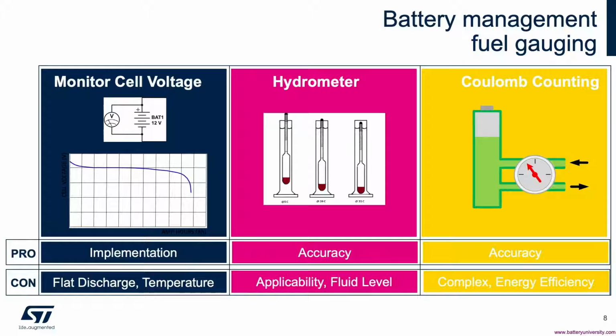First, mid-charge lithium-ion discharge curves are relatively flat, as shown. This necessitates the use of a very high-resolution signal path. In addition, cell voltage is impacted by load current as well as temperature variation, further complicating the issue. Most academic papers that address fuel gauging in a lithium cell suggest that the battery be unloaded for a long period of time before cell voltages are sampled.